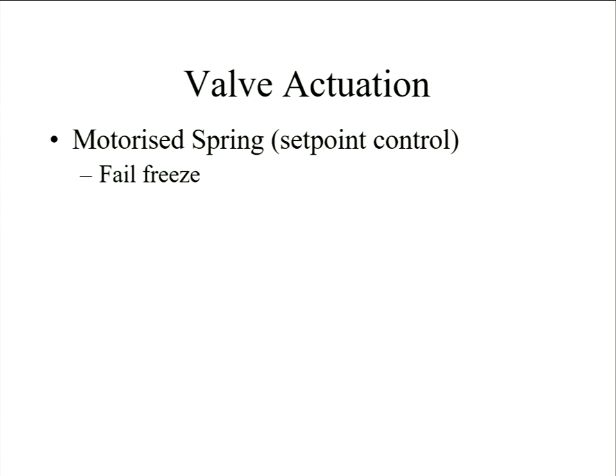A lot of regulators then use pilot regulators as a way of improving the control. That was a form of pilot with two diaphragms, and you could gas load one, and depending on how you load it, you can make it fail high or fail low. Or direct actuation, where you get more complicated actuators, pneumatic, electric, electro-hydraulic, with some form of actual valve position feedback.